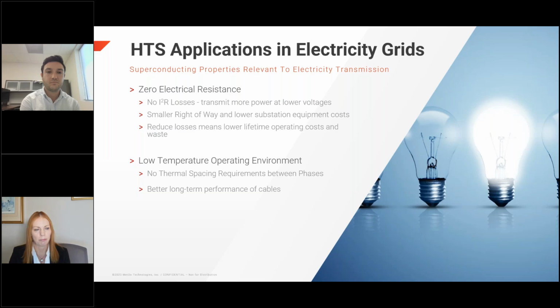But now, with materials like high temperature superconductors, if they don't have any I squared R losses, we can step back and think differently about how we design our grid. By having no I squared R losses, we can transmit a lot more power at lower voltages than we do today. And when operating at lower voltages, you've got smaller cables, smaller rights of way, and lower substation equipment costs. Not to mention that reducing I squared R losses has a lifetime benefit as well, a lower operating cost, and avoids the waste of energy.